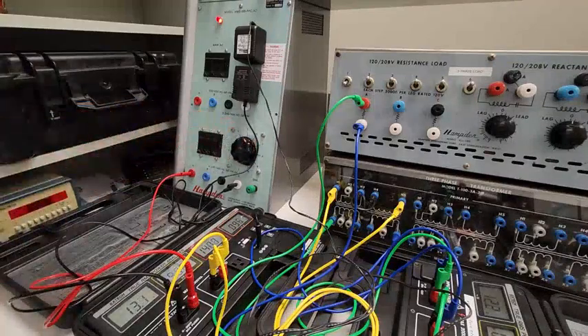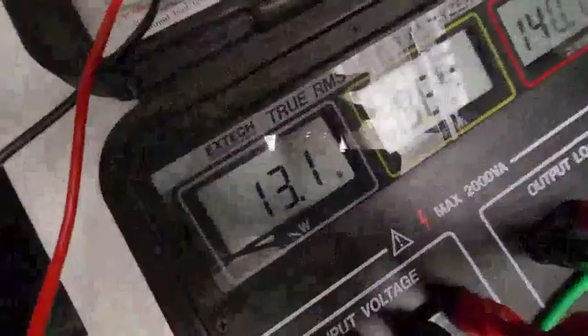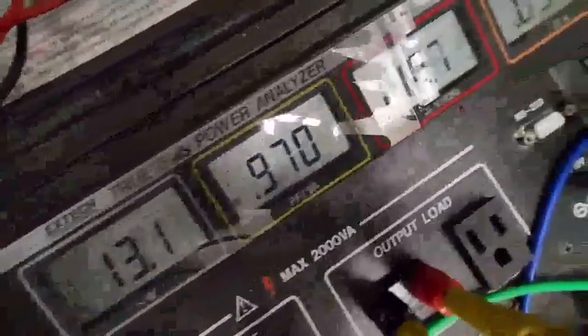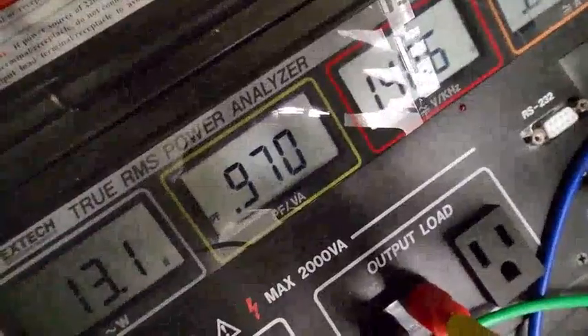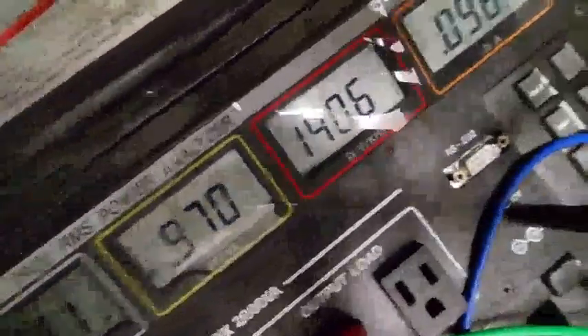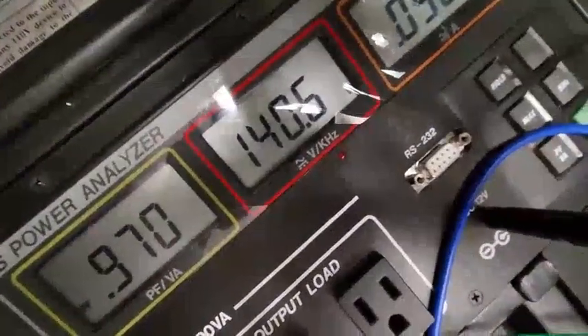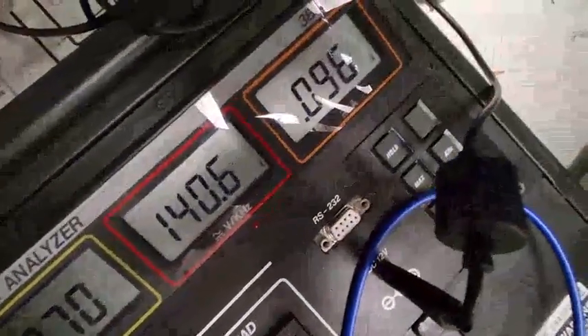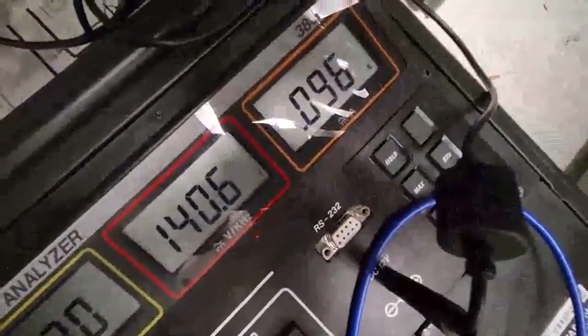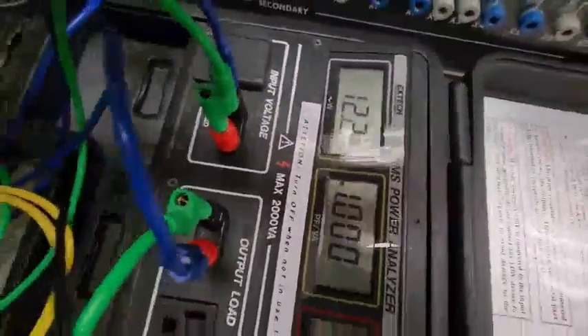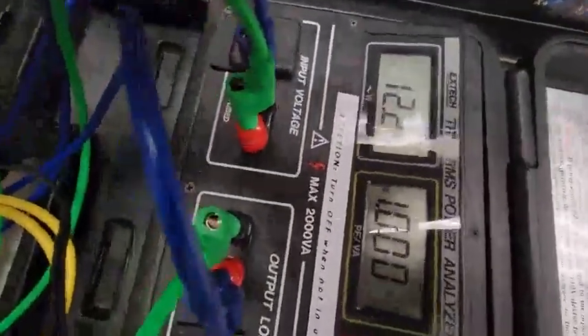Okay, I'd like you to take the reading. Primary side's power is 13.1, power factor is 0.97, the supplied voltage is 140.6, and the current is 0.096. On the secondary side, the power is 12.2 — there are some losses, a significant amount, about 1 watt loss in the system.